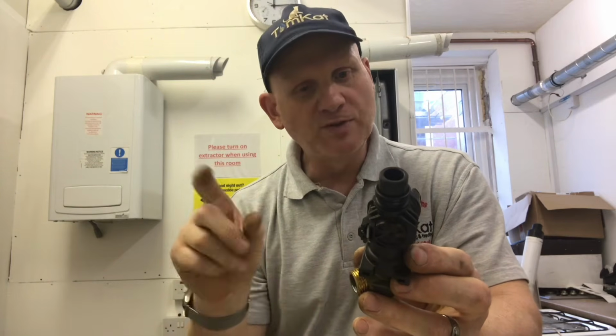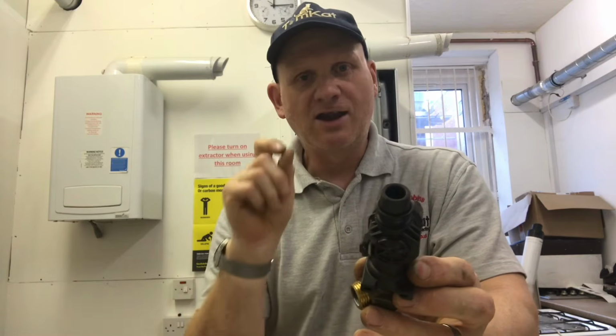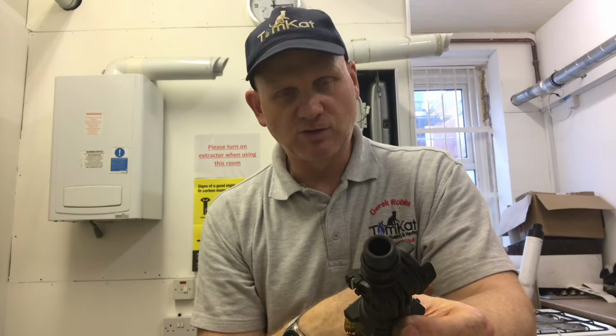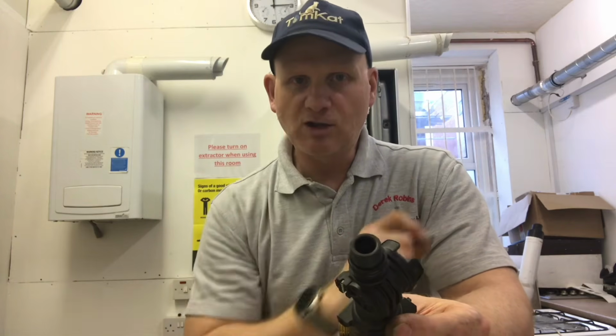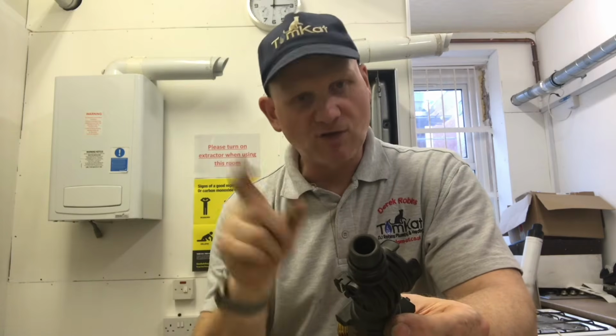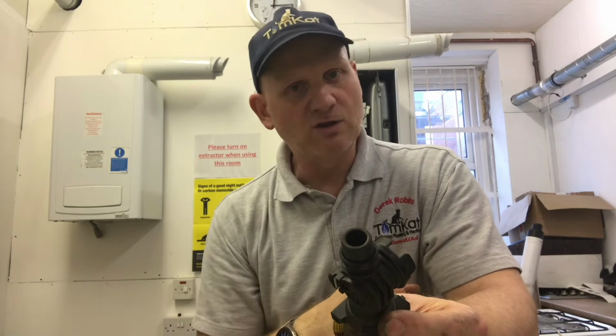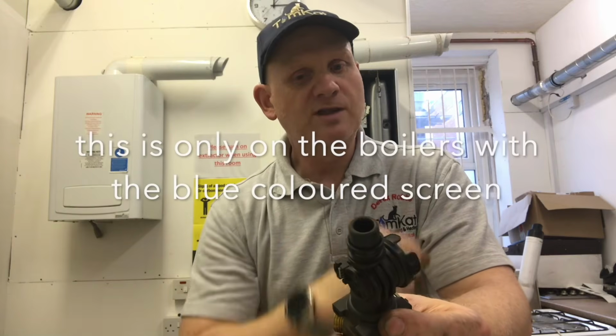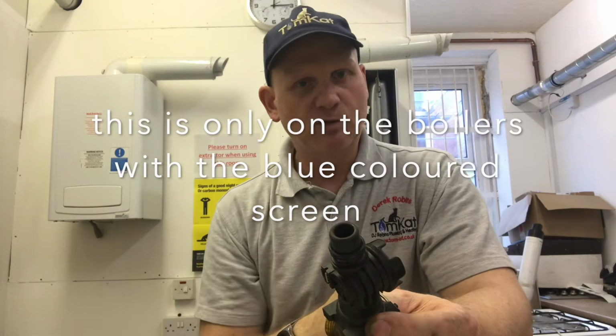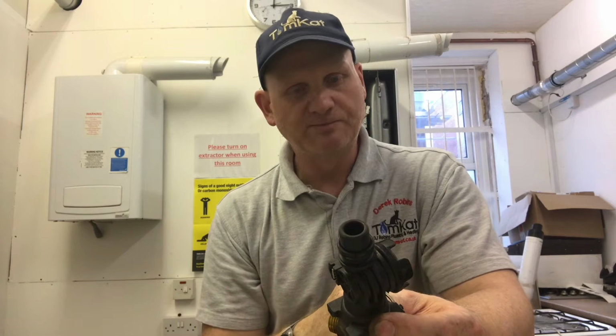The fault you would get with this is, if you open the tap and the water was running and on the display there was no little tap symbol, that would give you an indication that there's something wrong with the flow turbine. If there is a little tap symbol on the display when you've got the tap running, then it's not the flow turbine, it could be the diverter valve or something else. But this is how you can tell whether it's working. On the front panel, a little tap will come on when the water is running.